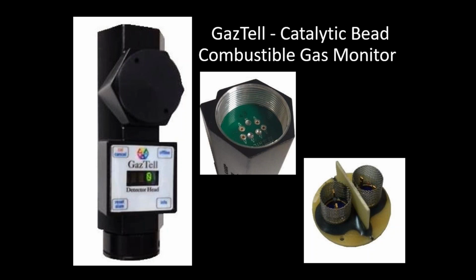The other thing we've improved over our latest catalytic bead sensors, if you notice, we've put screens around the catalytic bead reference and active beads, and this prevents big fingers from destroying the bead when you place the sensor in the body when you're replacing the elements. Very important, because we found that if you're not careful in handling a sensor, you have to remember that the sensor itself is the most fragile part of the detector head, and because it's a catalytic bead mounted on a 1 mil platinum wire, they can be damaged very easily by your finger, by a tool, by a screwdriver.